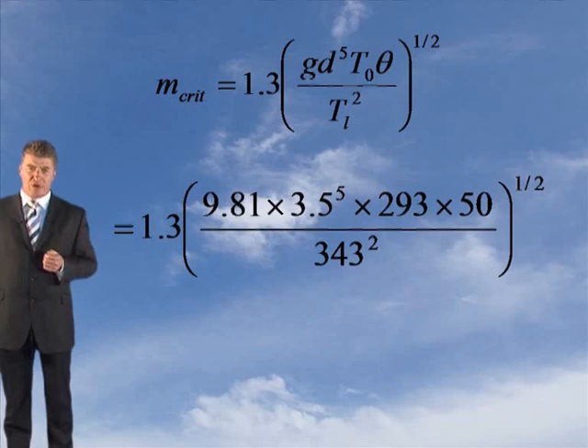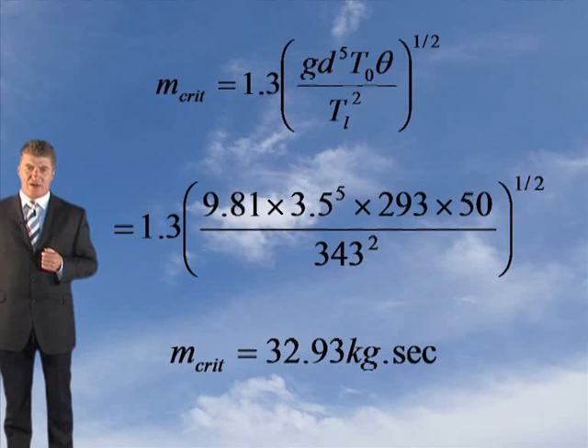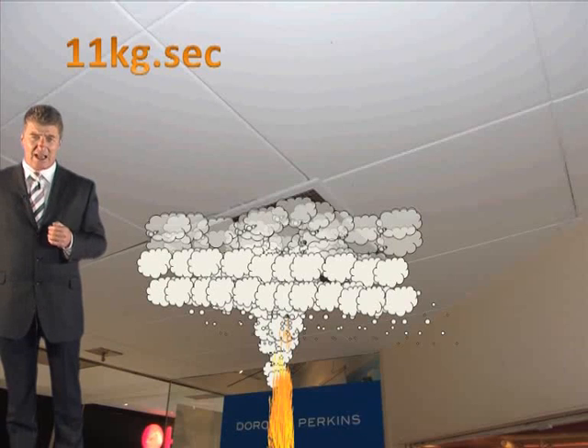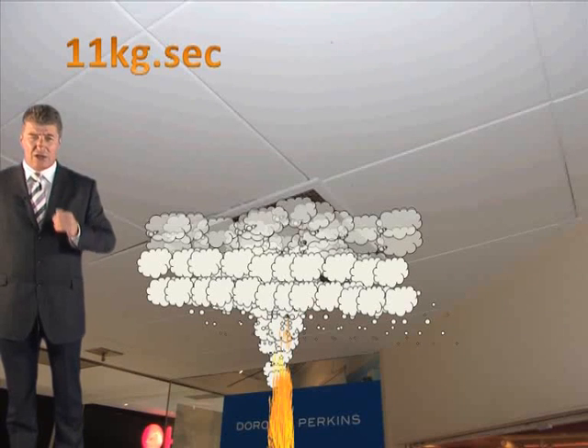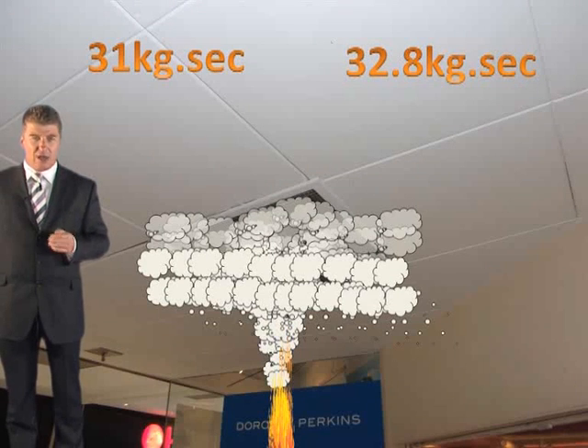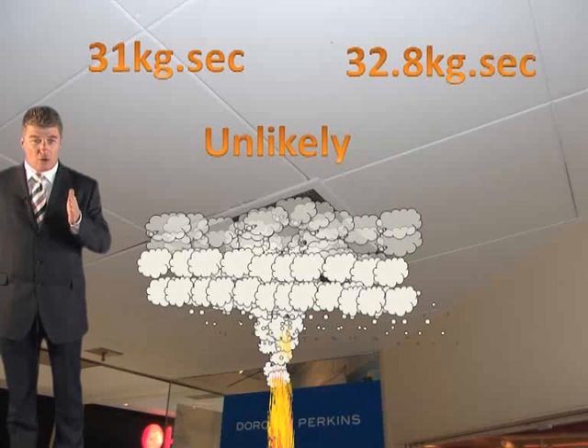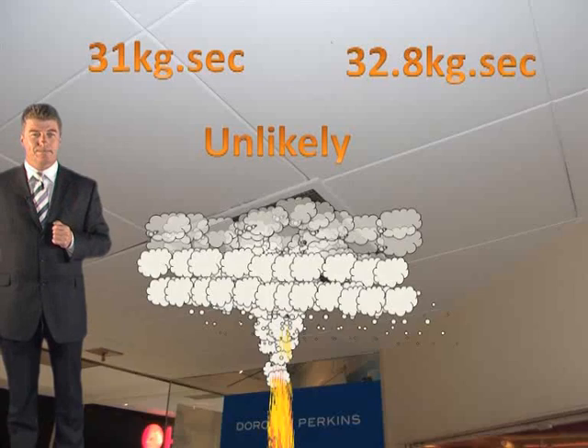Putting all known variables into that formula, you should have got an mcrit of 32.93 kilograms a second. So in this case, the smoke leaving each ventilator is 11 kilograms a second, and the mcrit is 32.93 kilograms a second, which means in this case, it is unlikely that plug holing will occur.